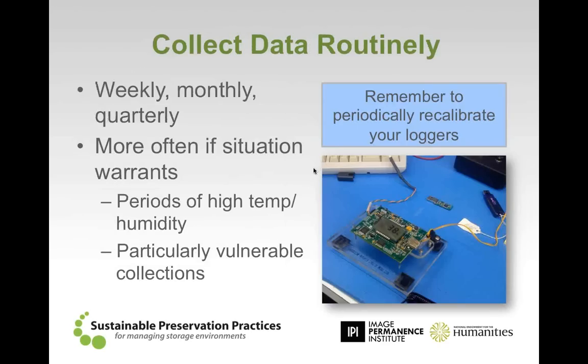When to collect your data, this is my last great question: how often should I collect my data? We have people who collect it weekly, or monthly. Some people have interns on hand who will collect data every day. I don't know of a logger that will punish you for over collecting your data. I haven't heard of one. It doesn't hurt to collect your data as often as you can, but whatever you do, try not to exceed 1 month. You want to make sure that at least once a month you're pulling that data from that logger.